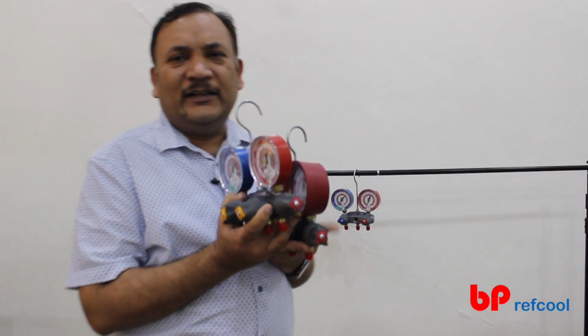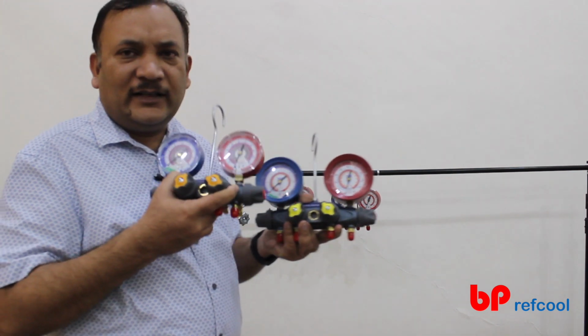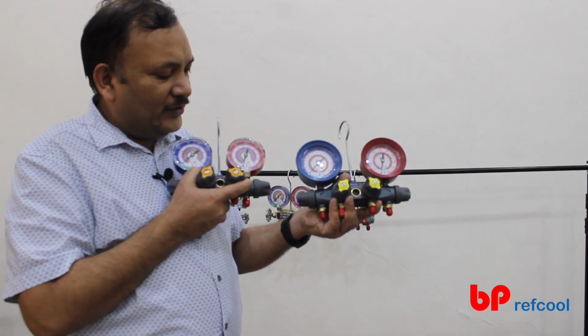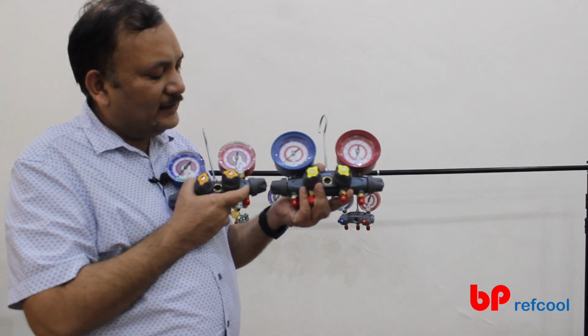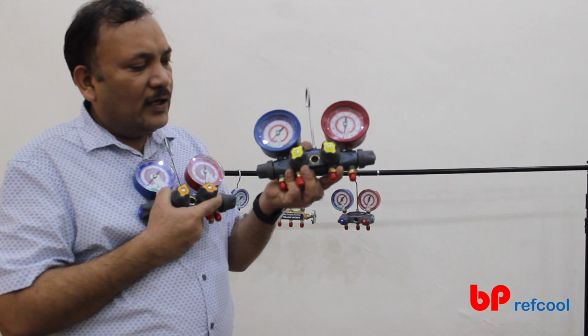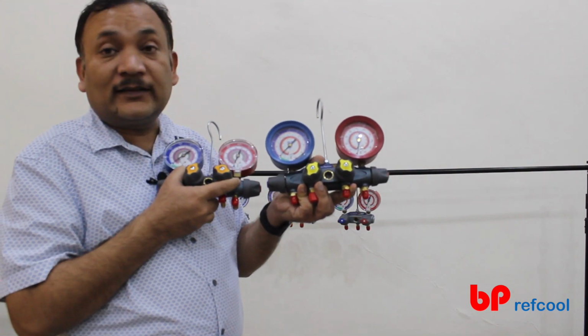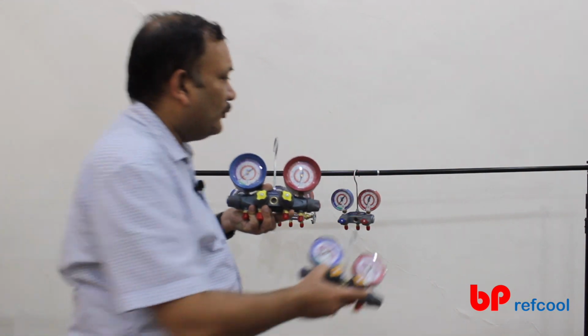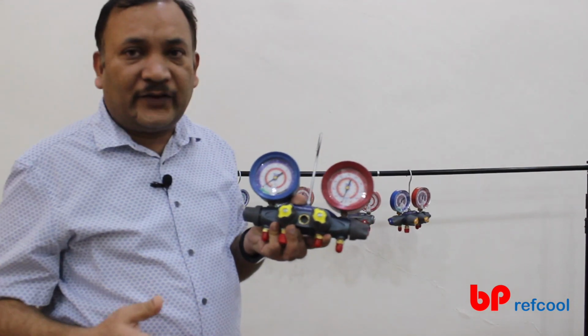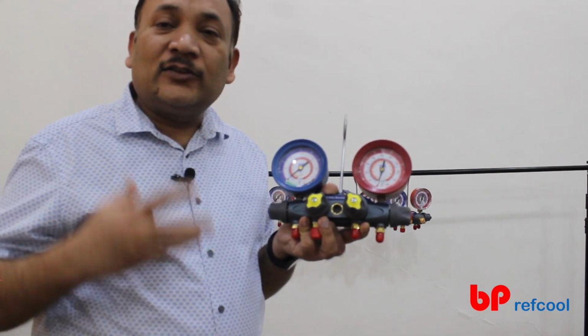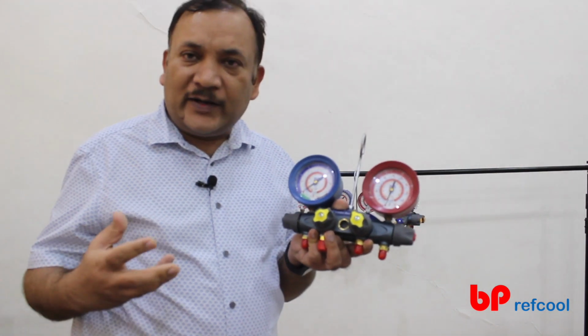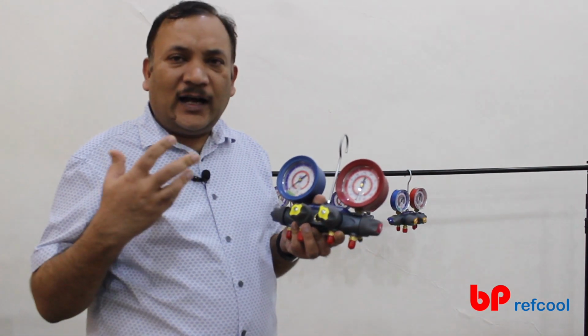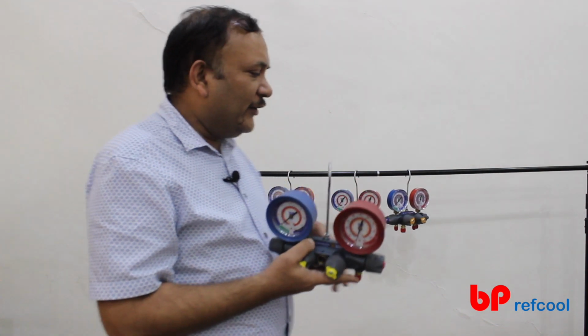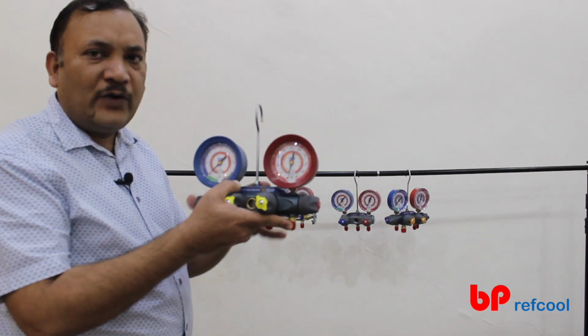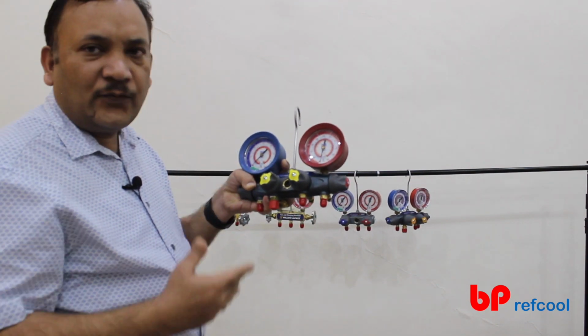Another thing, in case of a very high capacity chiller, while doing with this versus doing with this, this is Titan which has some size, and the bore of this is almost twice of this. So what this does is, when you're doing a vacuuming of a chiller or you're doing a gas charging or anything, this bore makes the flow of the gas or the vacuum very, very fast. So this makes the series complete, from a very small refrigerator to a very high capacity chiller of say 300 ton or 500 ton chiller.